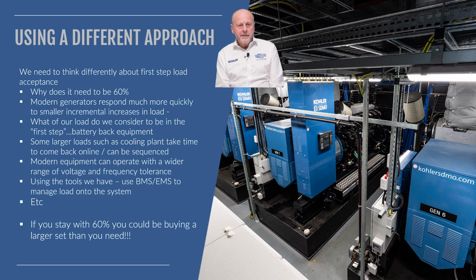So why does it need to be 60%? Modern generators respond much more quickly to smaller incremental increases in load. What of our load do we consider to be the first step? With much battery-backed equipment, which is prevalent throughout the healthcare setting, being one factor which will preclude it from being a first step load. Some larger loads, such as cooling plant, take time to come back online and can be sequenced. Modern equipment can operate with a much wider range of voltage and frequency tolerances, for example.